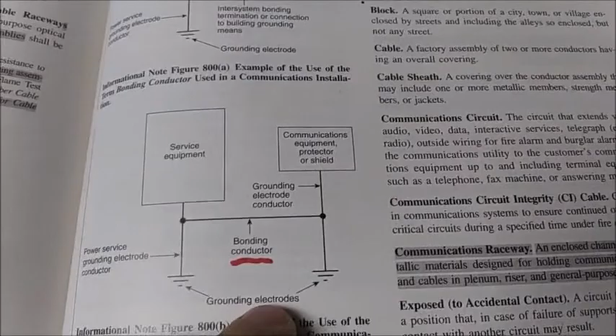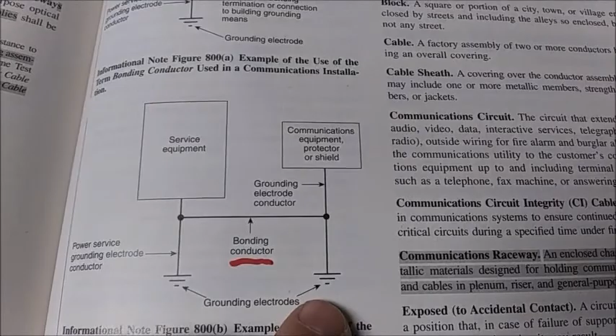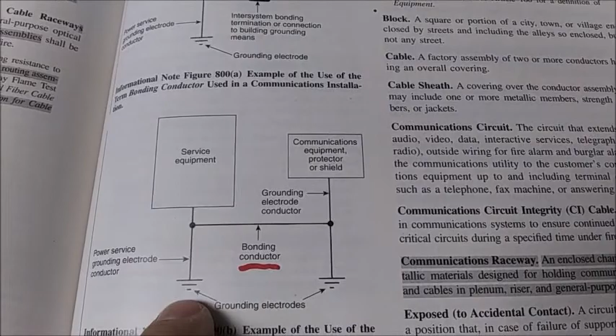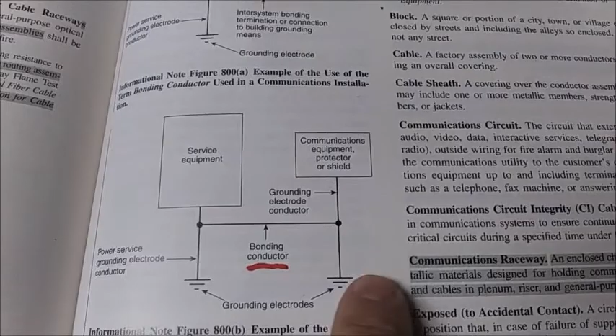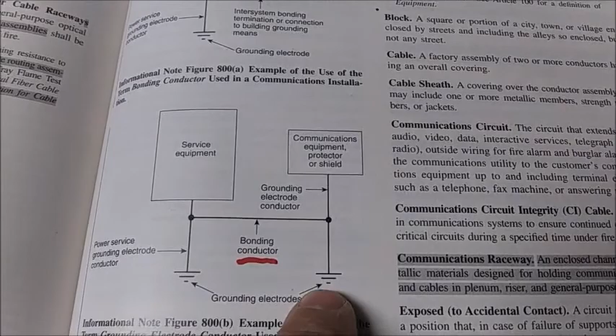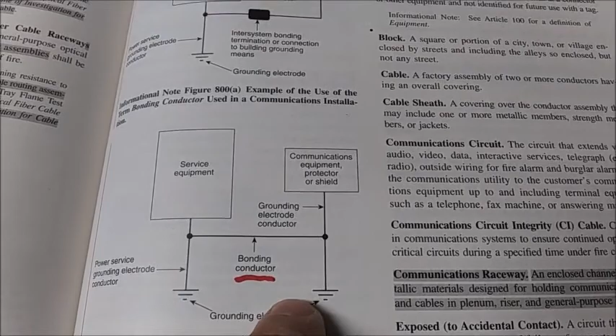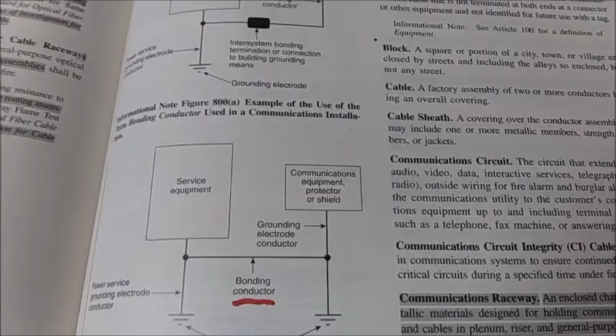This is where hams go wrong with grounding. There's a ham near me that took the advice of one of these self-proclaimed experts in grounding and put a ground rod, this one, about 100 feet away from the service entrance ground. And you know what he had for a bonding conductor? The antenna coax. And guess what happened when lightning hit the ground at this ground rod? And he showed me where it hit. What it did was create a very large current through the earth here. These 2 ground symbols imply that there's earth resistance between the 2, and it generated a very high voltage across the feed line. He was lucky he didn't lose all his equipment.